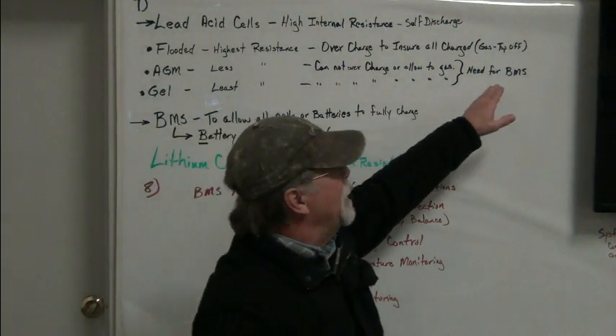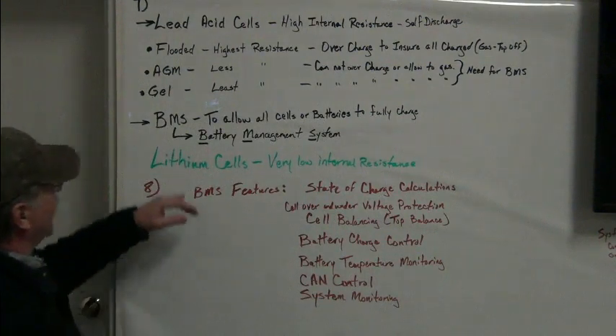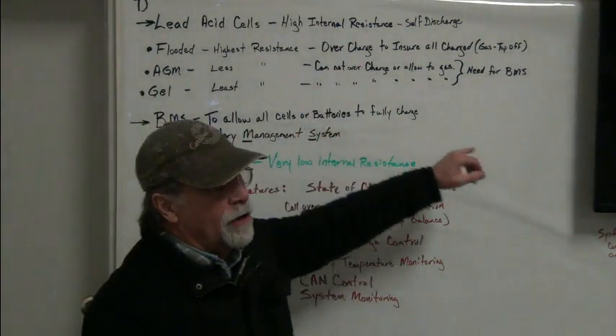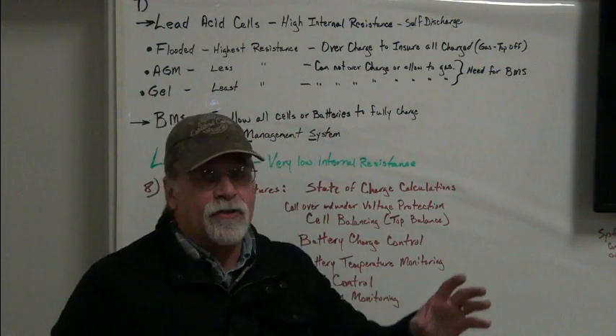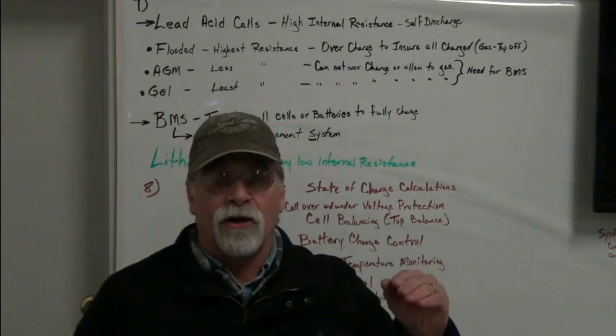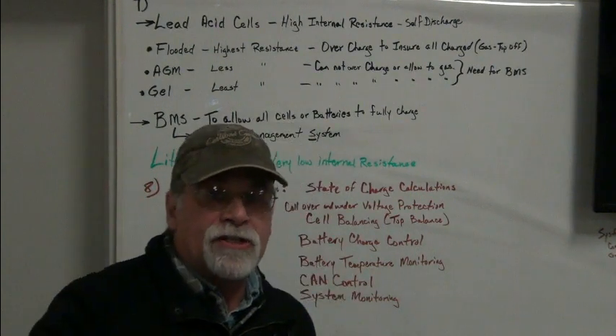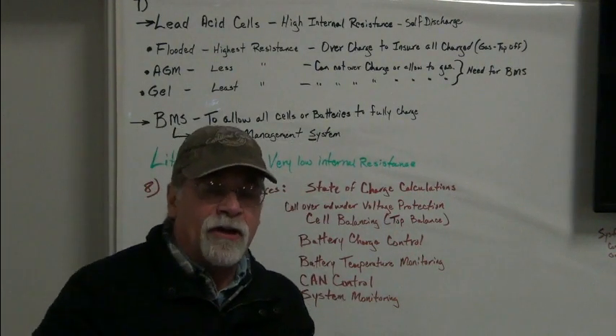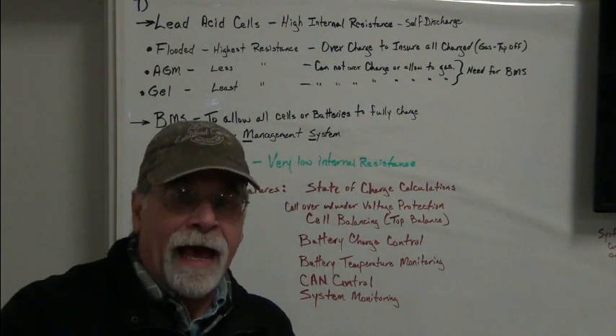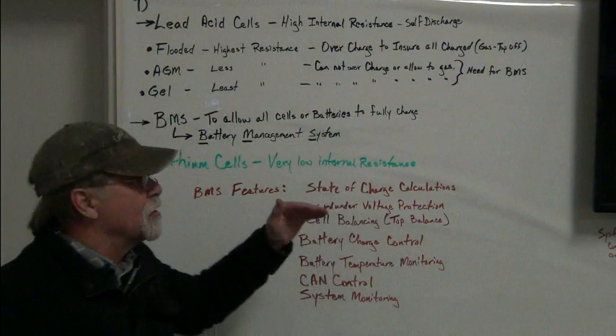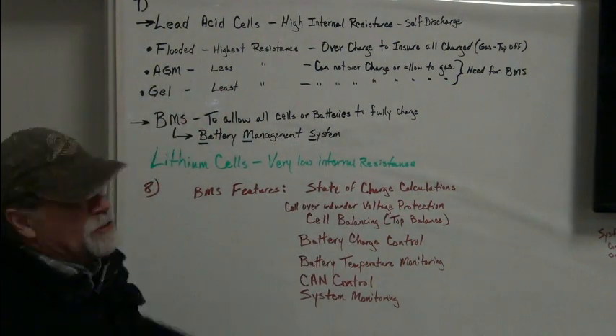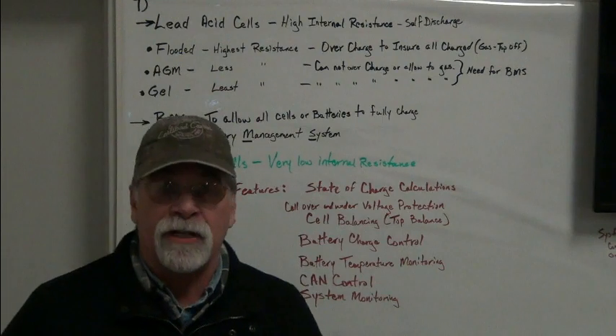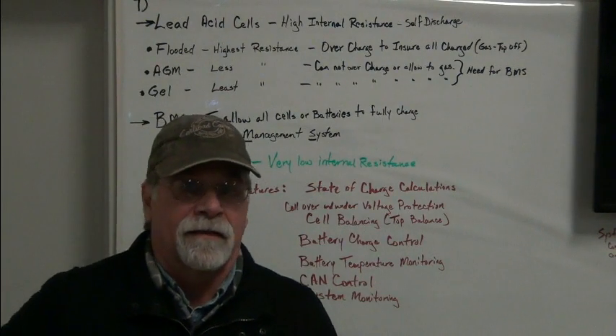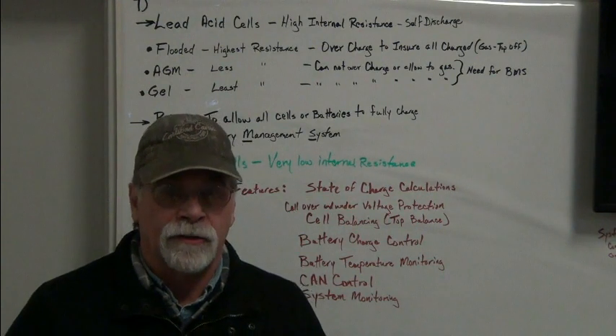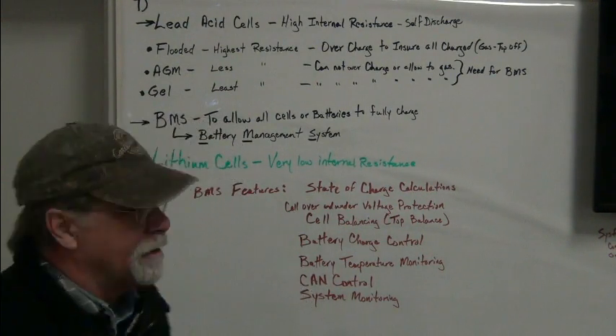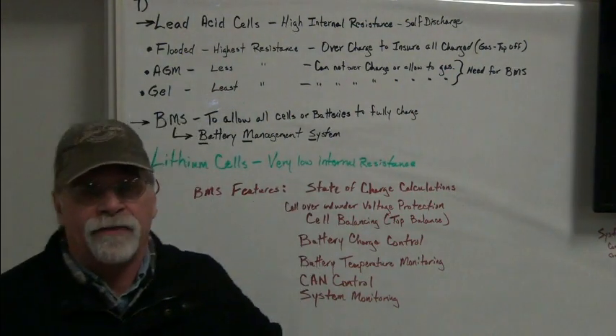So what the BMS did in those days was allow all the cells or batteries to fully charge by monitoring the individual batteries. When one of them became fully charged, it would bypass that one and continue to charge the others. Each time a battery got fully charged, it would shunt past that battery so it wouldn't overcharge. Because unlike the flooded cells, the AGM and gels, you can't replenish the electrolyte. So if they were to vent, they would lose electrolyte and lose life cycles dramatically. That's what a BMS was in the early days.